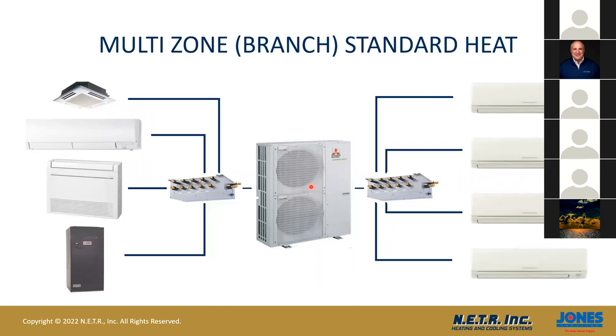This comes in all the way up to 60,000 BTUs. All right, so this goes up to 60,000 BTUs, which is 5 tons, which is a lot of heat, provides around 57,000 BTUs, I think, at 17 degrees. And you'll see this has multiple different indoor units. As far as what you can do, I've got a ducted unit here, a floor mount, wall mount, and then all wall mounts. Many different combinations of how you can put this together. It's what fits in your home and how it's going to work.